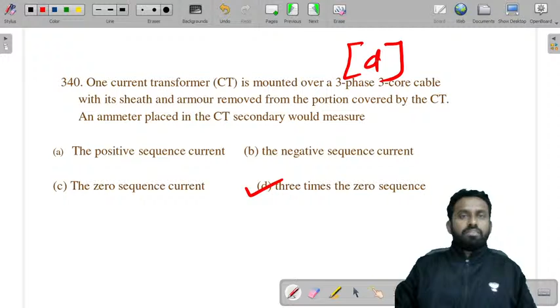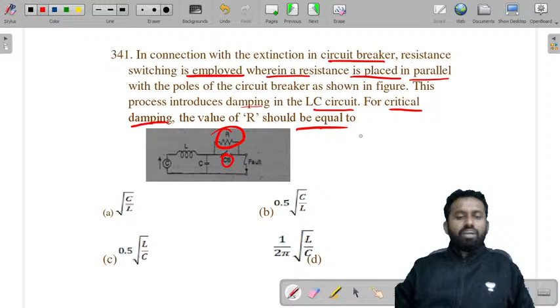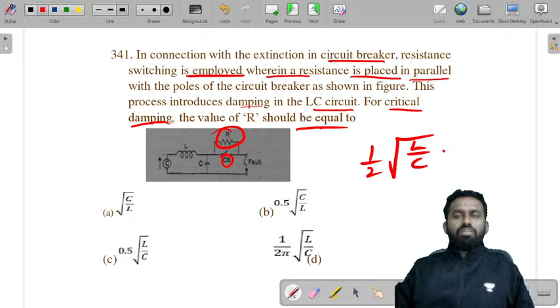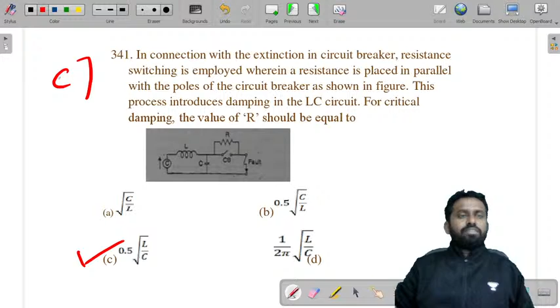Next question: In connection with extinction in circuit breakers, resistance switching is employed, wherein a resistance is placed in parallel with the poles of the circuit breaker, as shown in the figure. This process introduces damping in the LC circuit. For critical damping, the value of R should be 1/2 times the square root of L by C, that is 0.5 times root L by C. So the answer is C.